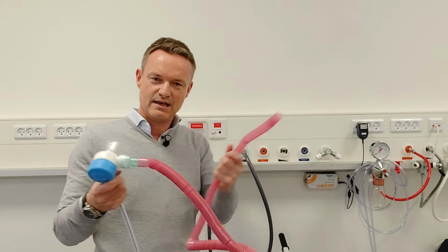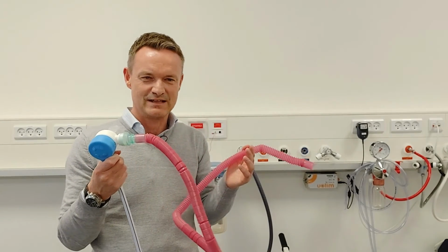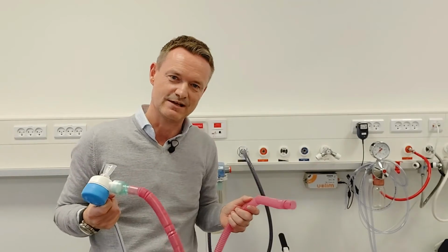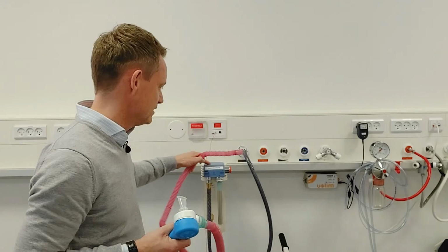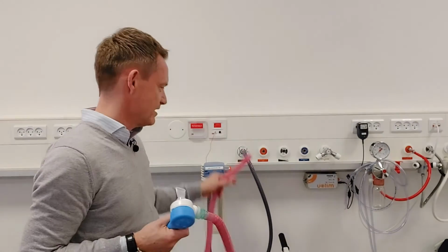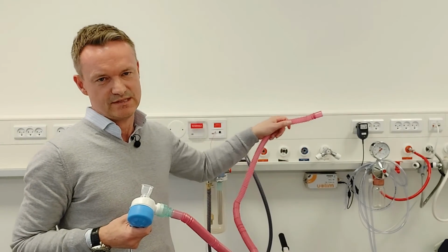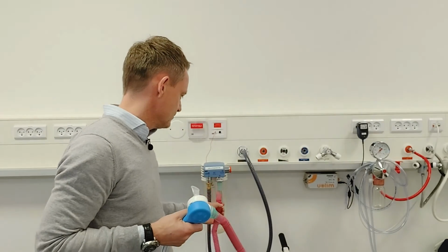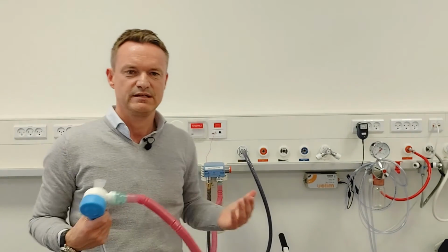So what I now need is to make sure that all the expired gas from the patient, which will contain nitrous oxide, of course, goes into my system here, which will then suck it up and lead it down to the AGS pump, which will then put it over to the central destruction system. So I place that here, and what you have now is a complete system, right?